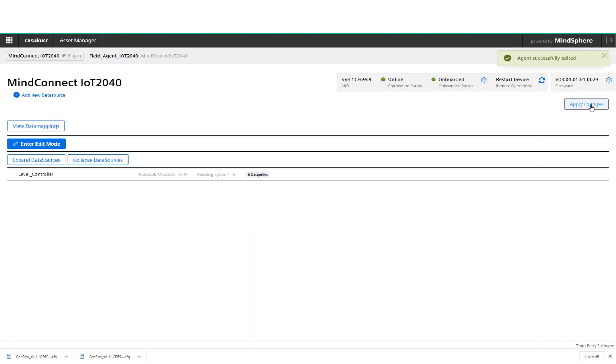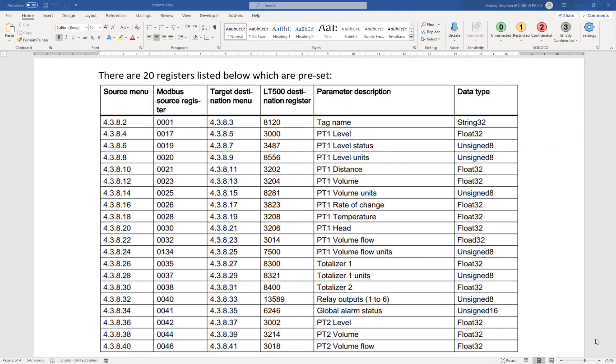The next stage is to add the information that we want to read from the device. For Modbus that is held in certain registers: the coil register, the input/output register, and a lot of data is output into the holding register. The holding register supports real words — floating point words. For the connected instruments you are going to require the Modbus memory map. For this particular level device everything is held in the holding register, which starts with a 4.